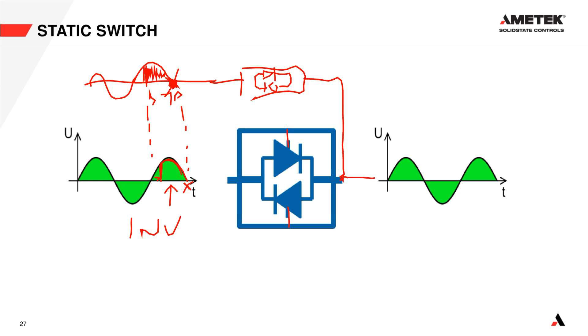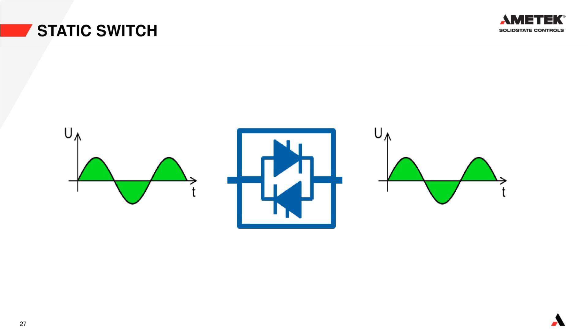So what that allows us to do is have a seamless transfer every single time between bypass and inverter when they are in sync, because you cannot switch an SCR off instantly, it will only switch off when it gets to its zero crossing point. So whenever you turn it on, you are going to have two AC supplies in parallel for a very short period of time, which gives you the security of knowing that your loads are going to be maintained at all times. Hopefully I made that clear.